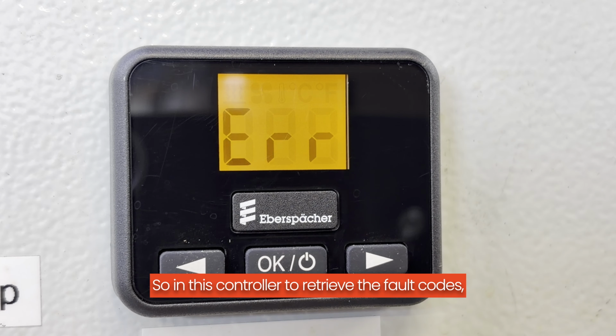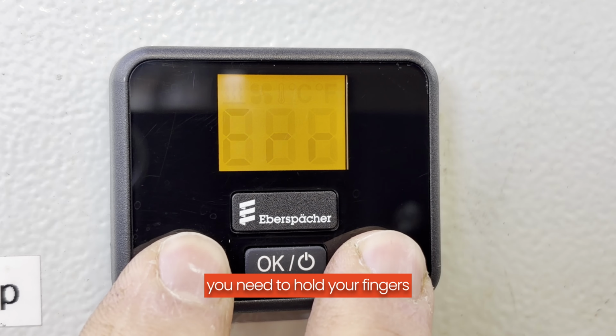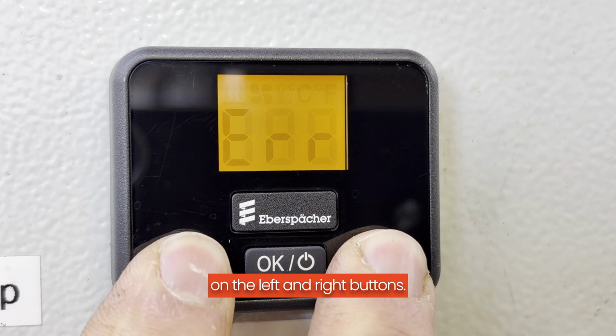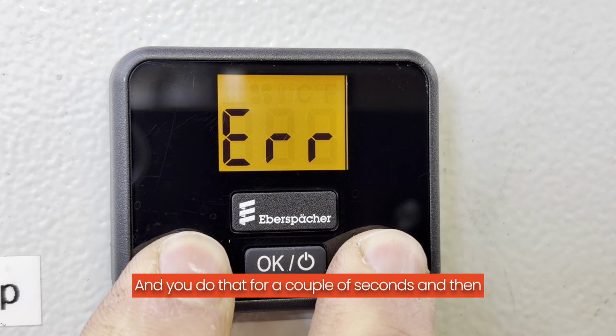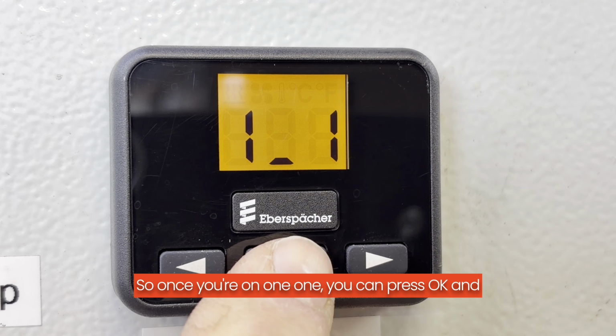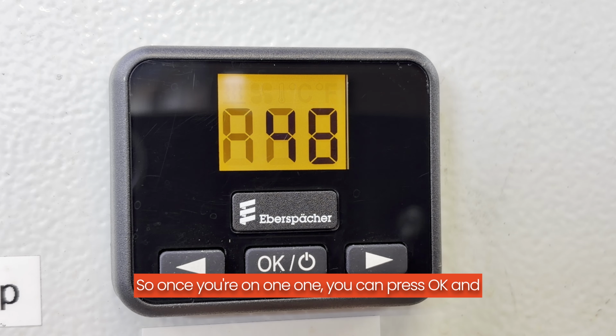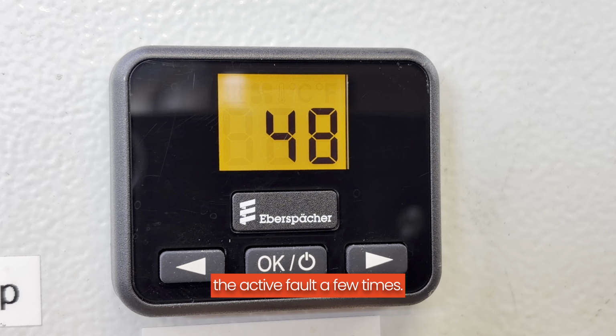So on this controller, to retrieve the fault codes, you need to hold your fingers on the left and right buttons, and you do that for a couple of seconds, and then it's going to bring up 11. So 11 is the active fault. So once you're on 11, you can press OK, and the controller will flash the active fault a few times, and then it's going to revert back to the 11 menu when it's showing you what the active fault is.